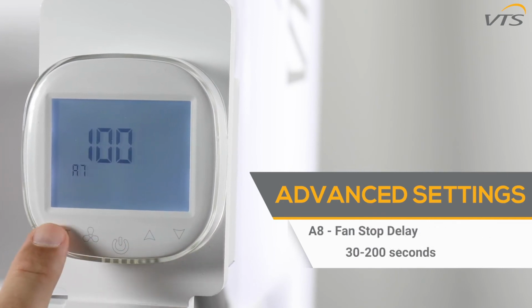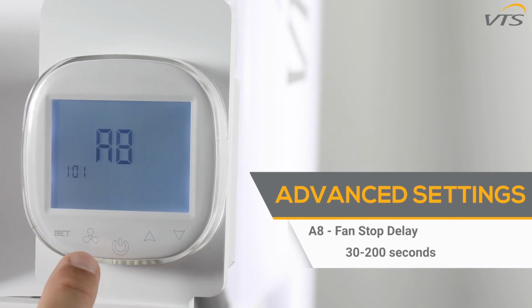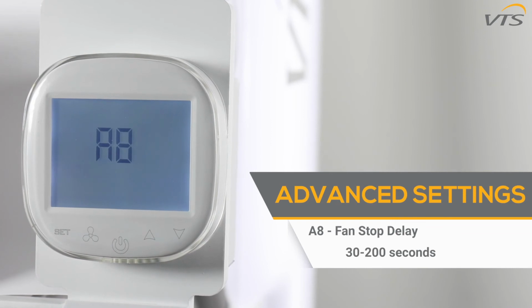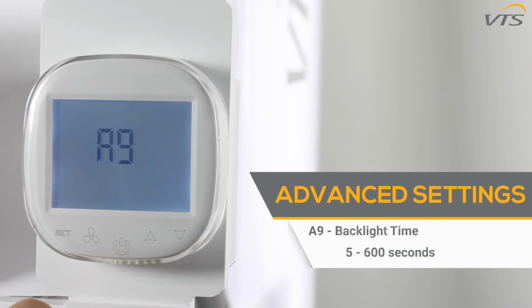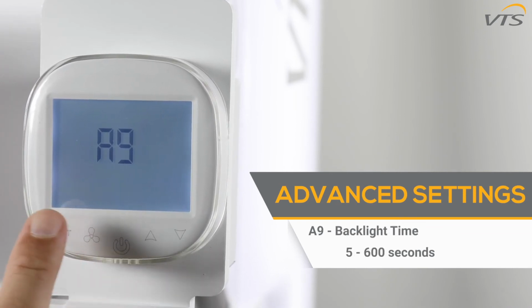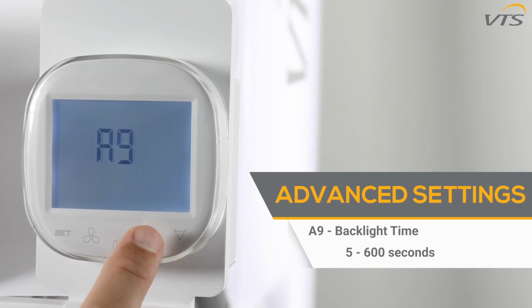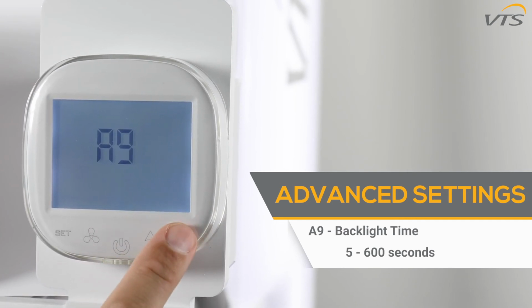The A8 function allows you to set the fan stopping delay time from 30 to 200 seconds. The A9 function controls how long the backlight stays on for the controller. You can select between 5 and 600 seconds.